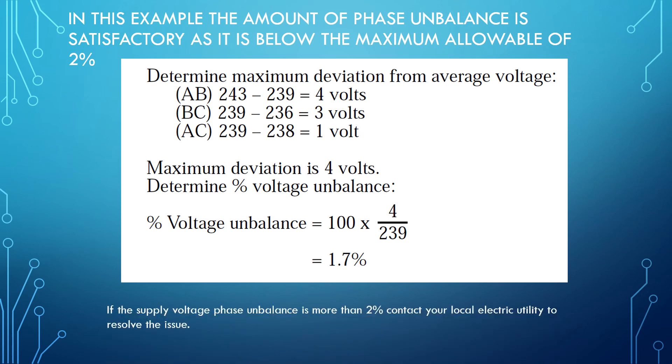If the supply voltage phase unbalance is more than 2%, contact your local electric utility to resolve the issue.